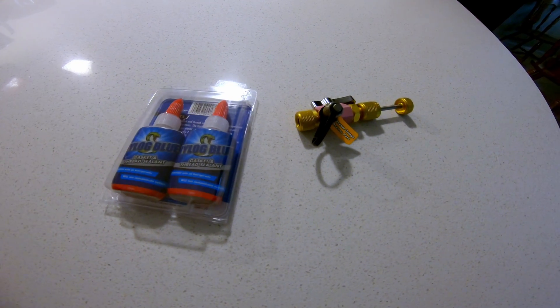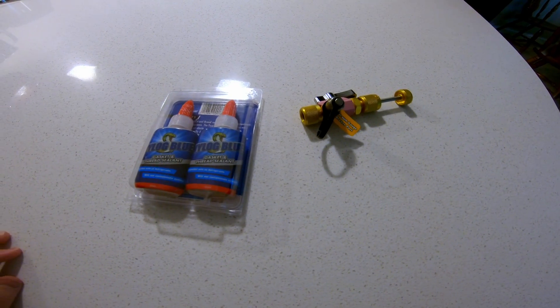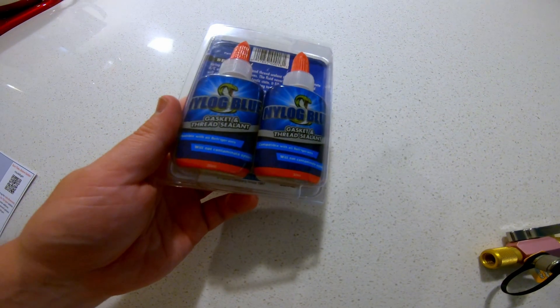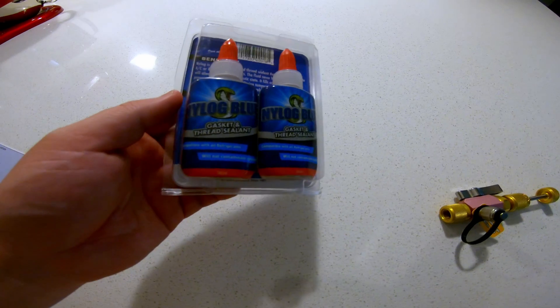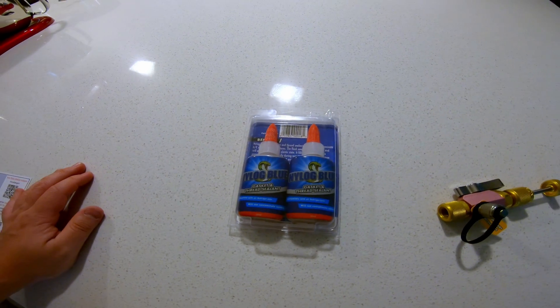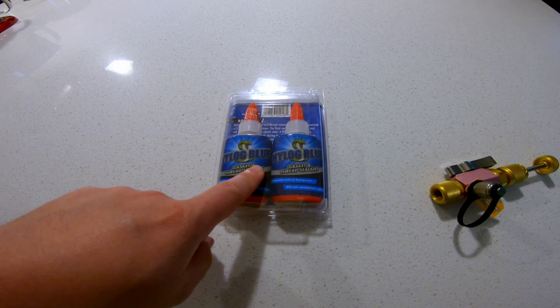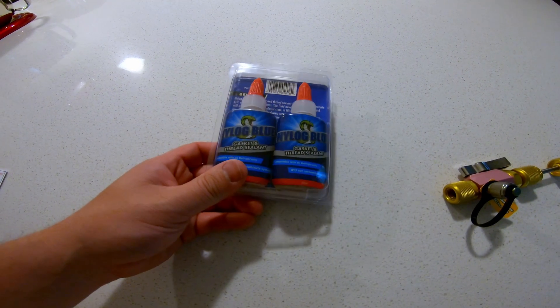Two last critical pieces of equipment I think are 100% necessary for a mini split installation. This nylog is absolutely a must for the flares. My tool makes beautiful flares and I think they would certainly hold, but I've never had any flares leak when I've used nylog, even after numerous years. It's definitely worth the investment — a little goes a long way and it lasts a long time.